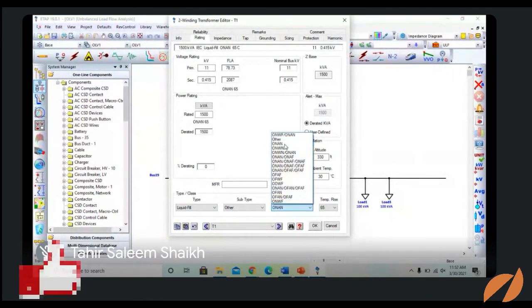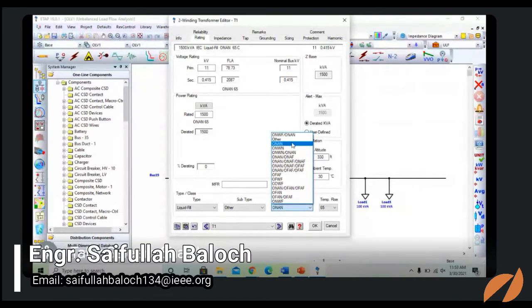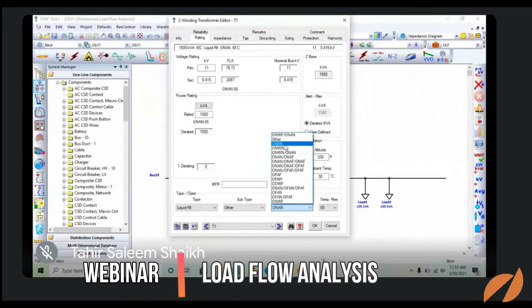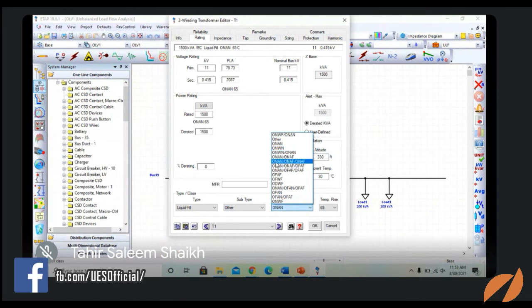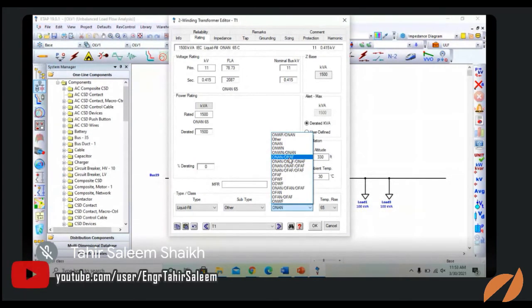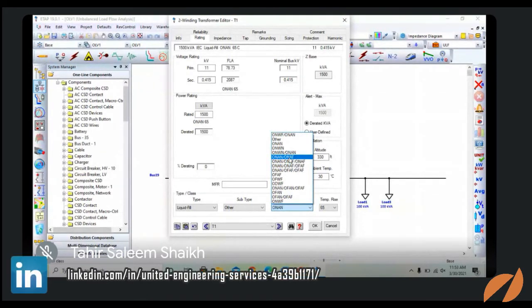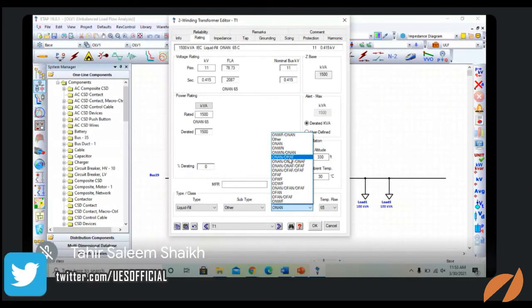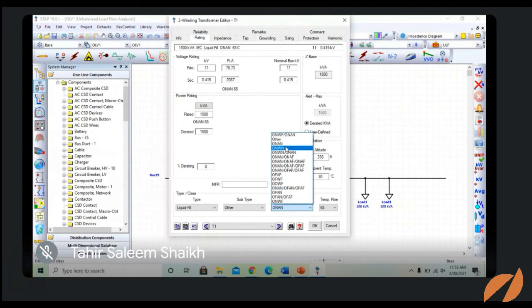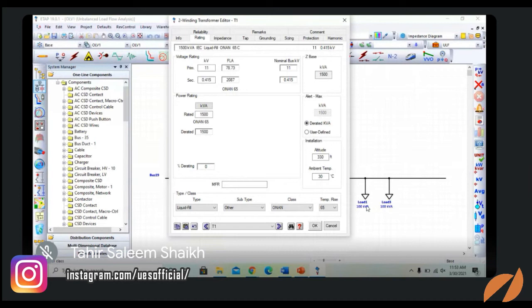Okay, class. Here we have different classes of cooling, referring to the cooling class: ONAN, oil natural air natural, and oil natural air forced. Oil is naturally flowing in the transformer, and air forced means fans are installed near the transformer to blow a huge amount of air. Yes, forced draft fans are used for the cooling system. So here we have a basic one, that is oil natural air natural, like the distribution transformer.